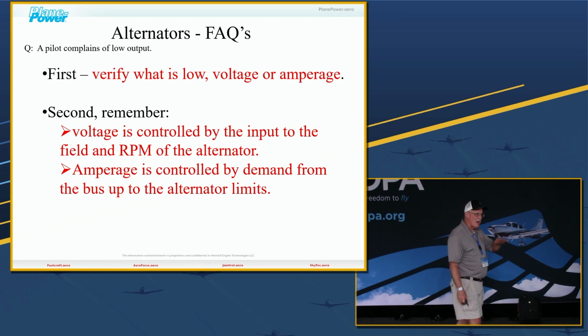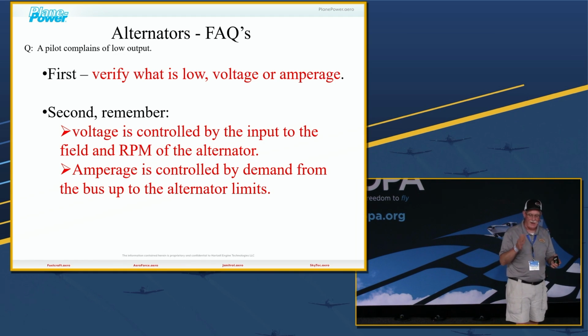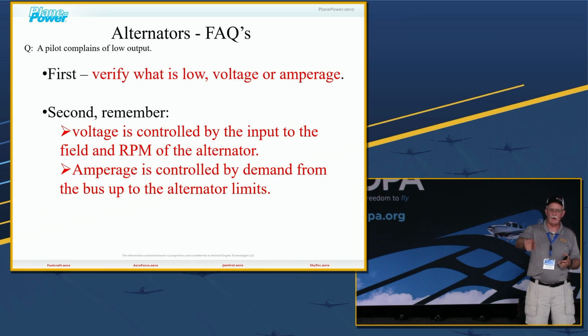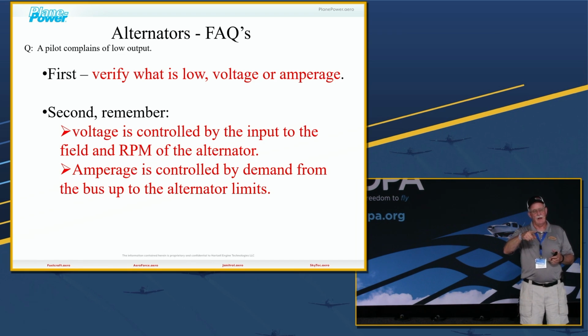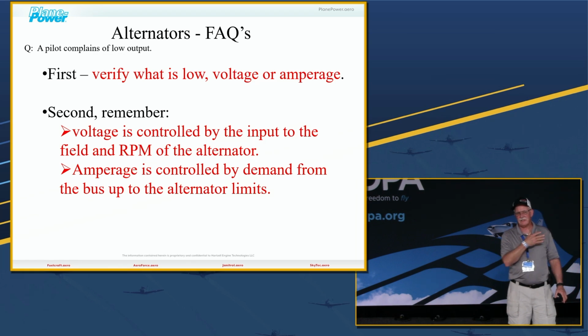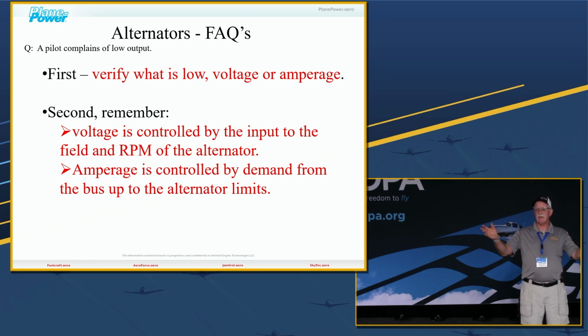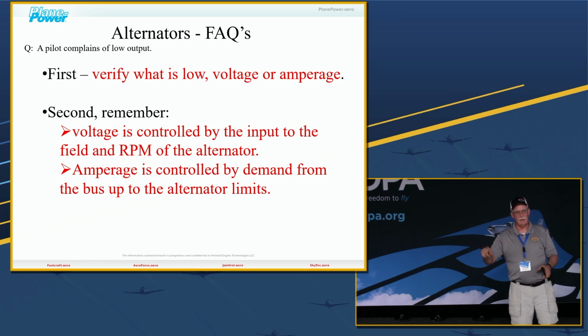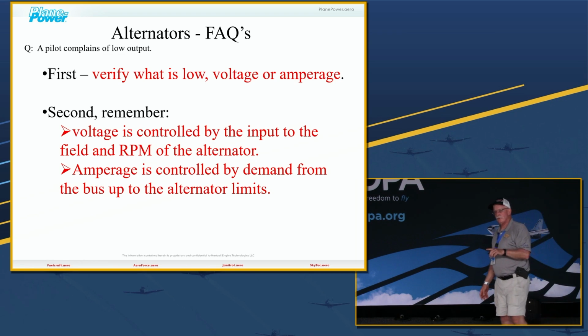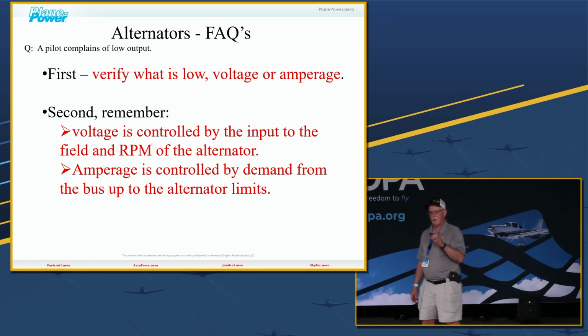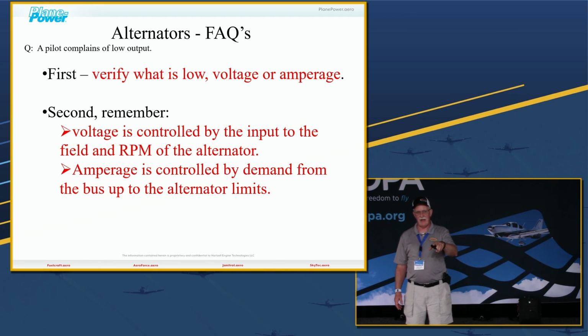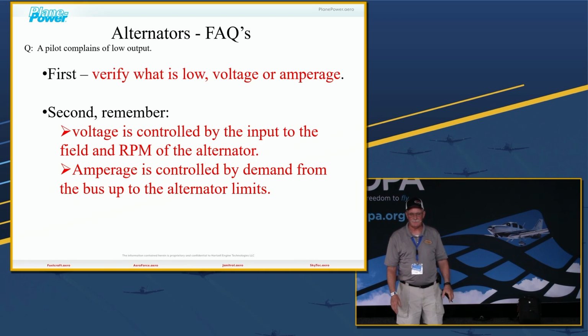So you've got to remember the voltage is controlled by the input from the voltage regulator and the speed of the alternator. The amperage is controlled by the bus. The bus itself says, hey, this person has turned on these switches, and those switches add up to a continuous load of 27 amps. The alternator will now supply 27 amps, and the voltage regulator will maintain that at 14.2 volts.